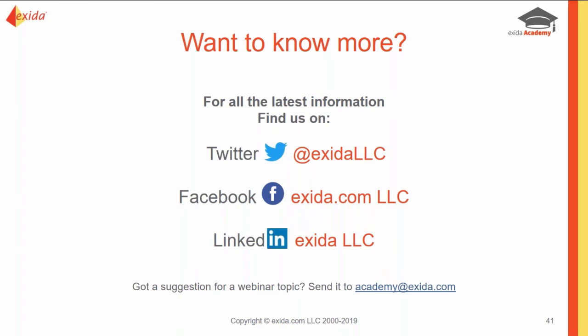The next question we have is if we physically test the products for families. It depends on what type of certification you're going for. But for IEC 61508, we do not. We will do the FMEDA analysis by looking at a drawing and a BOM, and we will look at your validation and verification test plans and reports. We do not do the physical testing for IEC 61508.